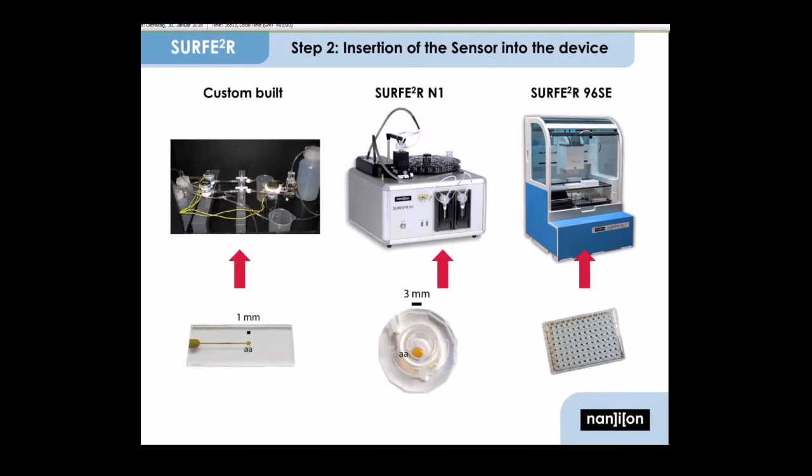Once the sample is prepared with the SSM and the sample on top, it is inserted in a SURFE2R instrument. This instrument contains a shielded measurement chamber, an advanced fluidic system, and all necessary electronics for recording and amplification. Here we can see on the right side our two SURFE2R instruments.